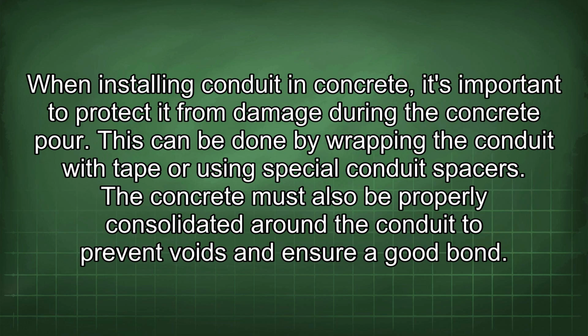When installing conduit in concrete, it's important to protect it from damage during the concrete pour. This can be done by wrapping the conduit with tape or using special conduit spacers. The concrete must also be properly consolidated around the conduit to prevent voids and ensure a good bond.